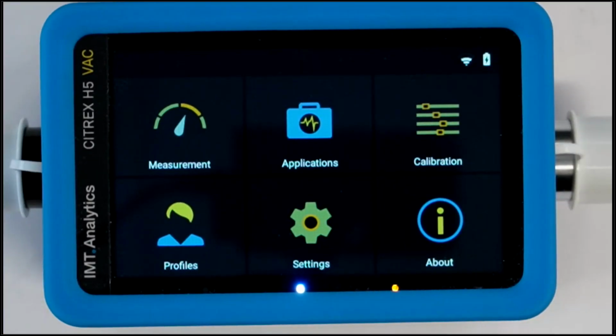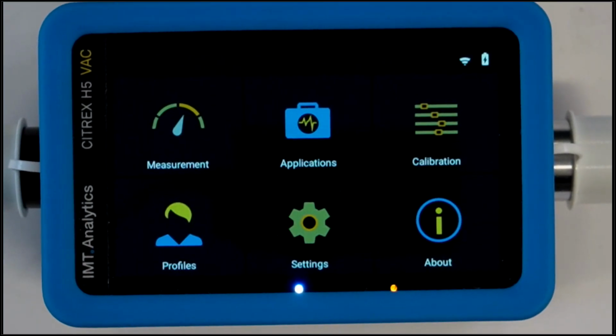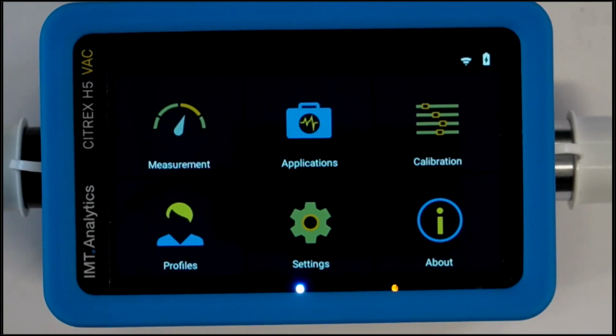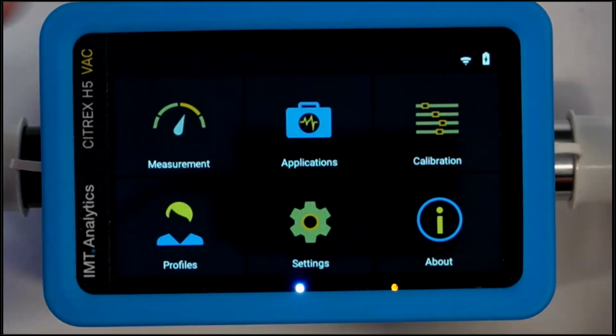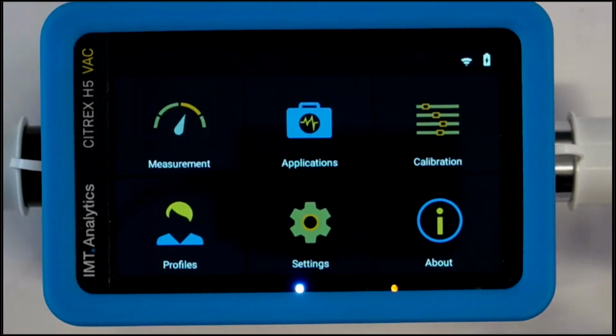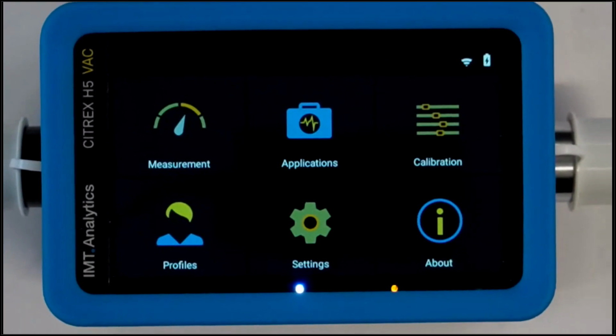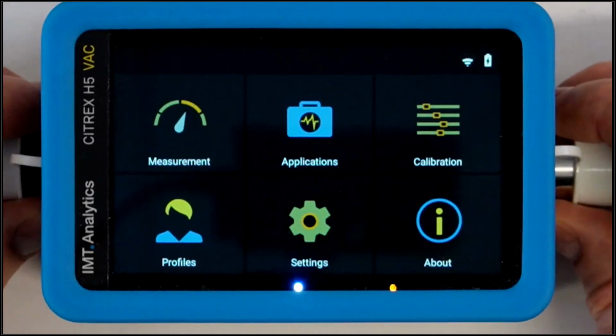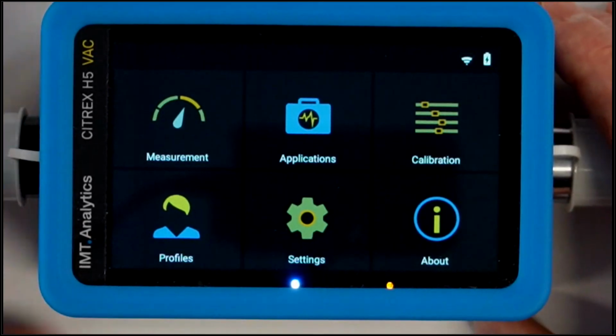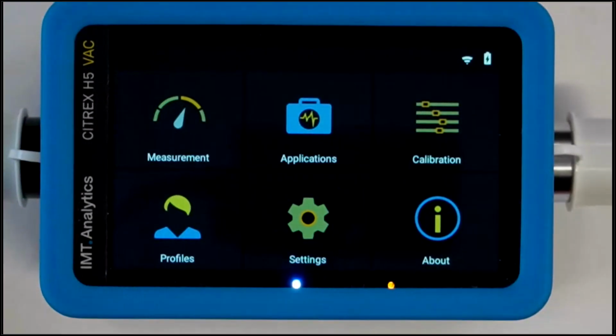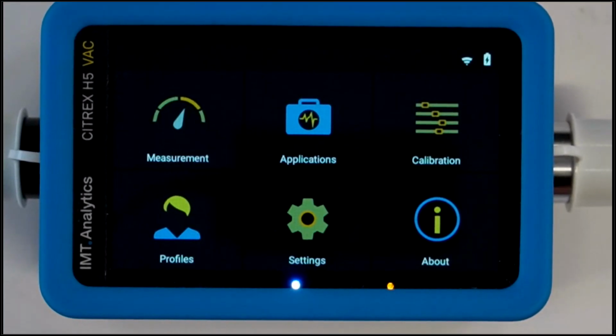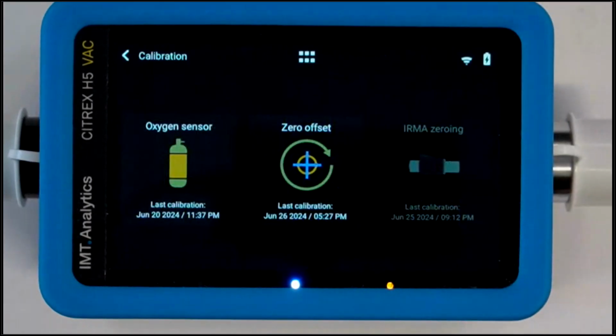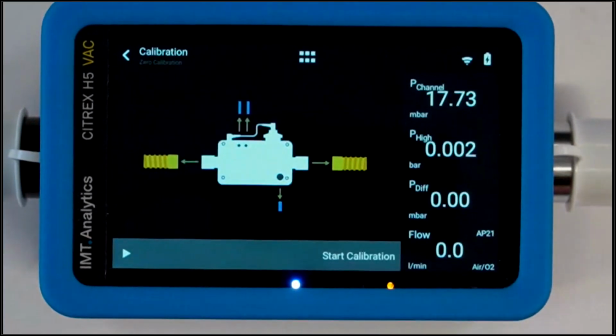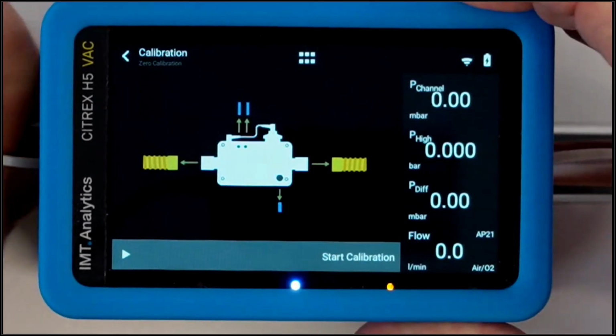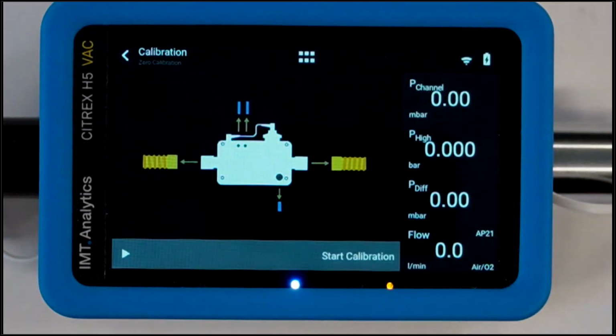All right, so let's talk a little bit about the H5 itself and its home screens and all the other navigation aids that you might want. As Daniel showed you, when you turn the device on, it comes up to this home screen that has 6 tiles. We'll get into each one as we go, but one of the things that you want to do with the H5 and any analyzer that you use is prepare it for testing whatever you happen to be testing. And with the H5, the first thing we want to do is turn it on and warm it up, which it is now. And the next thing we want to do is go to our calibration screen and select 0 offset. It says here in the diagram that you should disconnect any tubing that you might have on the device, so it's open to atmosphere.